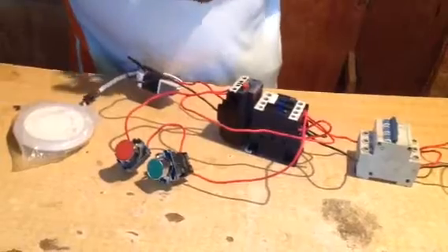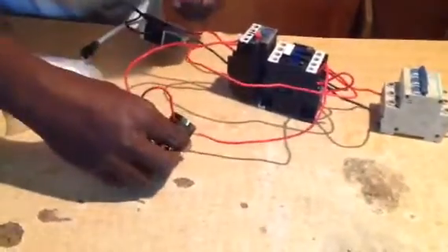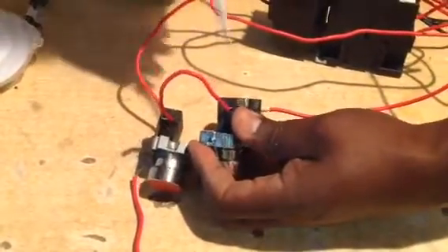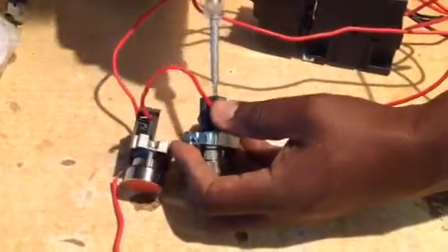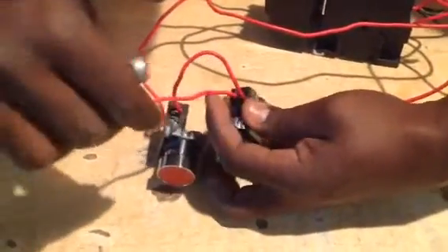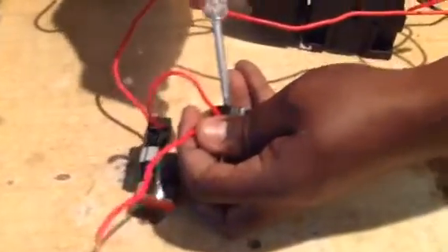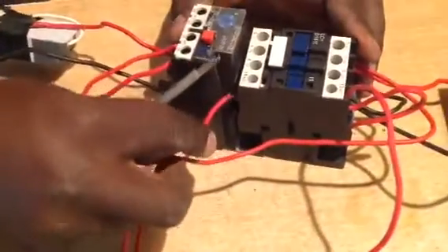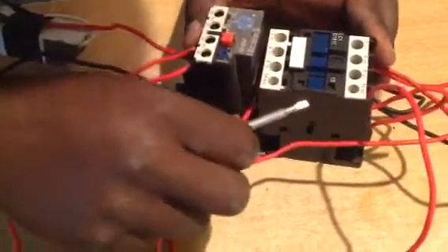We want it to self-hold for a machine that takes long, works for longer hours, longer minutes. So you introduce another wire. So you will go to either number 3 or number 2 up here, you add another wire. So you open here, you have to switch off first. So you put another wire from here, number 3. You can put it either from number 3 or number 2, and then you connect it here, number 14 down here.